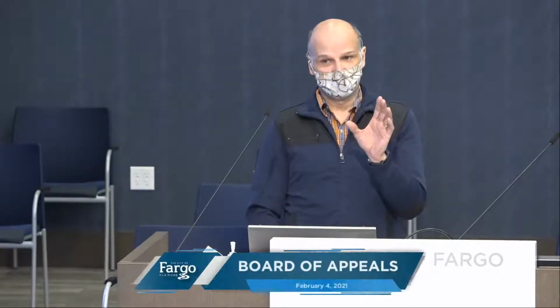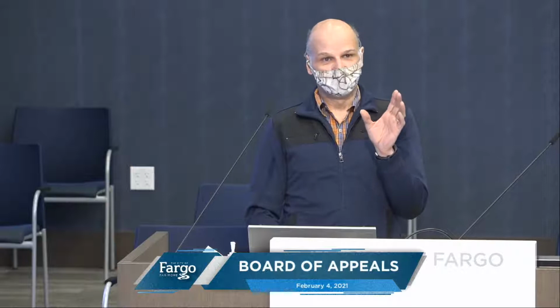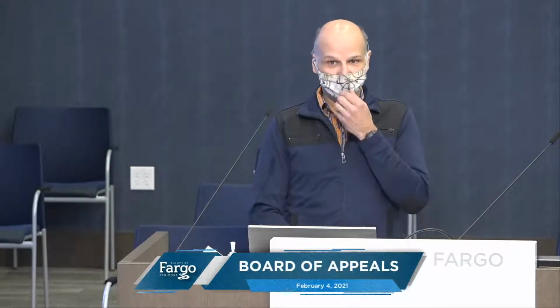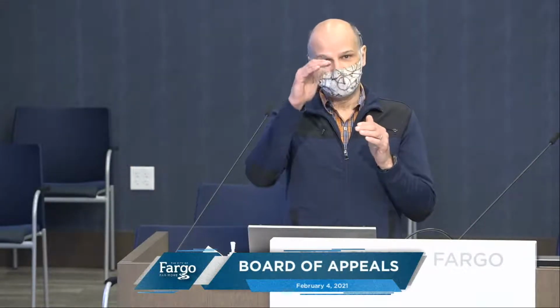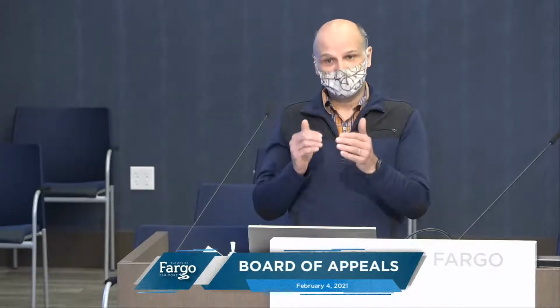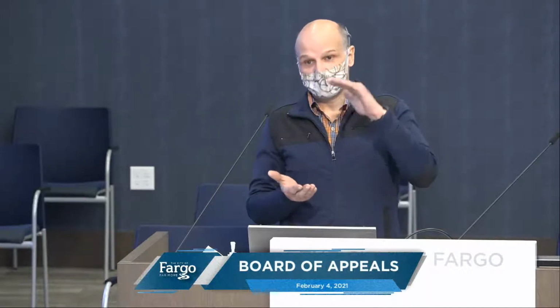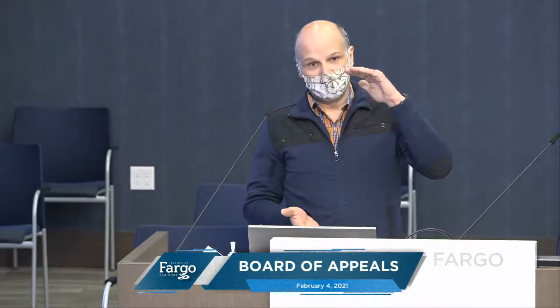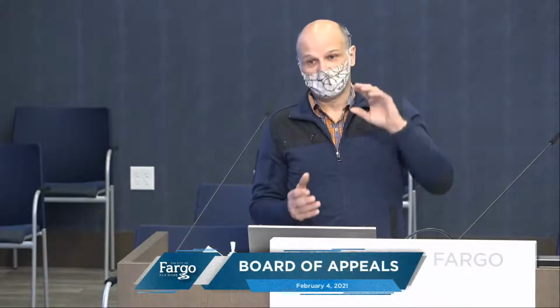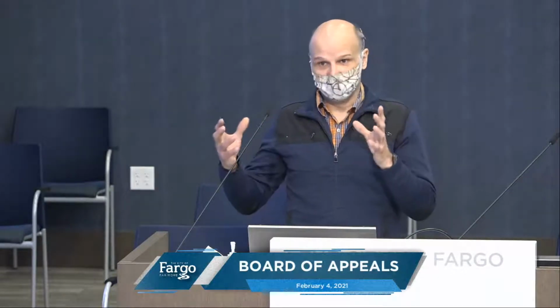Could I provide a little additional information on that? The code really is quite clear on that. It's straightforward math. 20% is required to be open. In no way does the addition of our garages impinge on the 20% requirement. The floors from story to story, there are different floor to floor levels, and consequently there are slightly different open calculations for each of those.